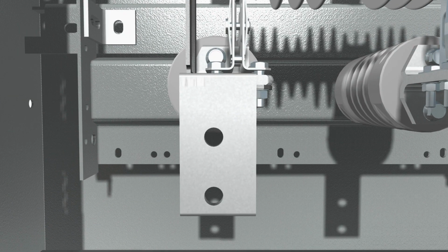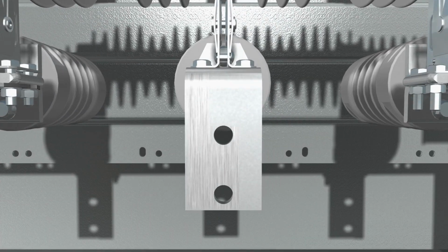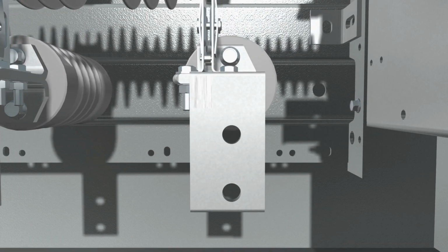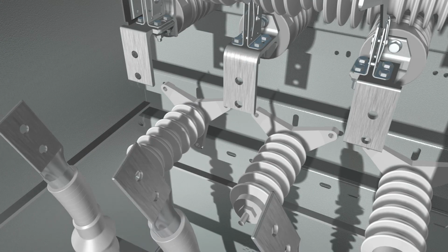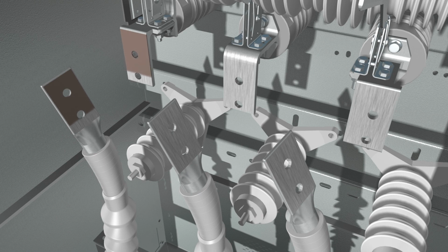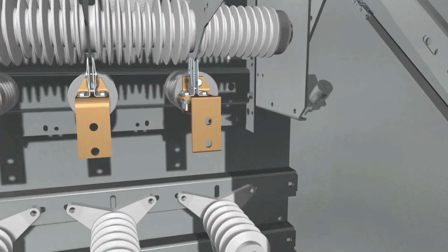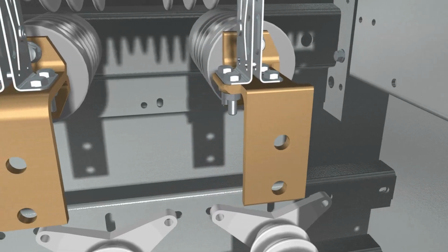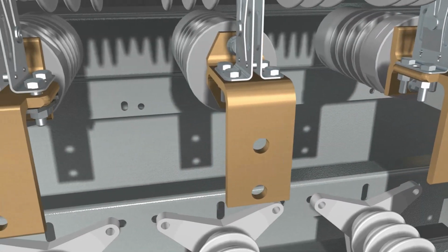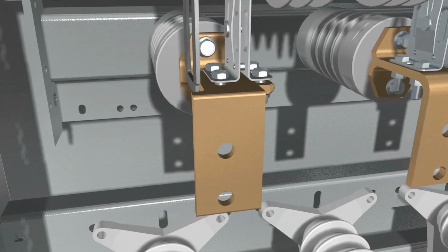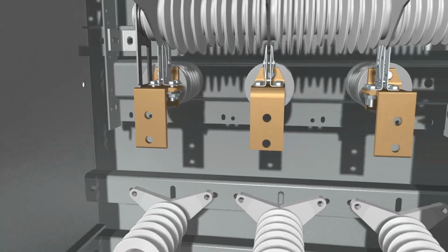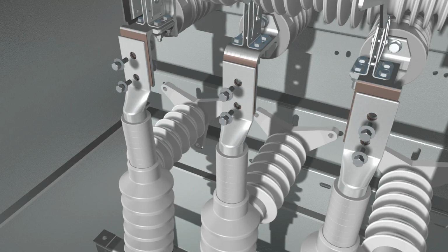Step 16. Before connecting the cable terminators to the terminal pads, thoroughly wire brush the aluminum contact surfaces to remove any dirt or foreign materials, as well as the natural surface oxides. Immediately coat both contact surfaces to 1/2 inch, 13 millimeters, beyond the joint with a uniform layer of Penetrox A. Note that copper terminals have a thin layer of silver applied to contact surfaces, and the terminal surfaces must be prepared as described in the note on page 16 in Step 9 of the written instructions. Step 17. Connect the cable terminators to the terminal pads.